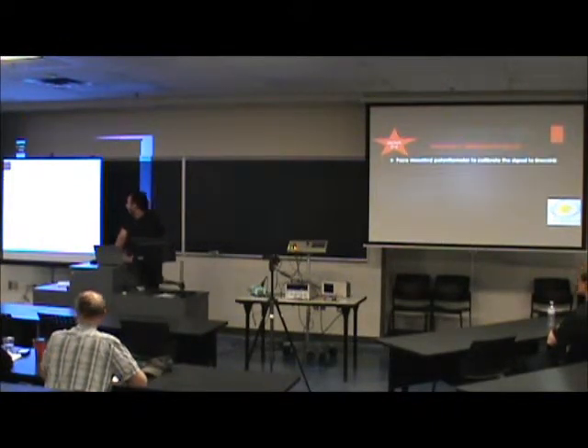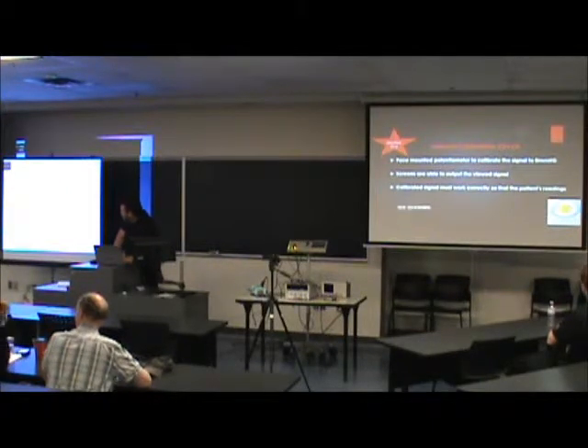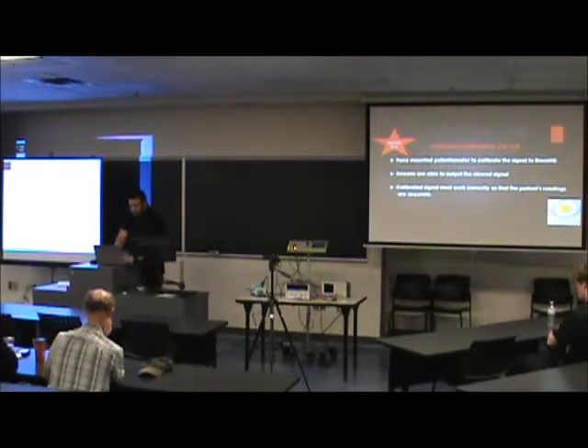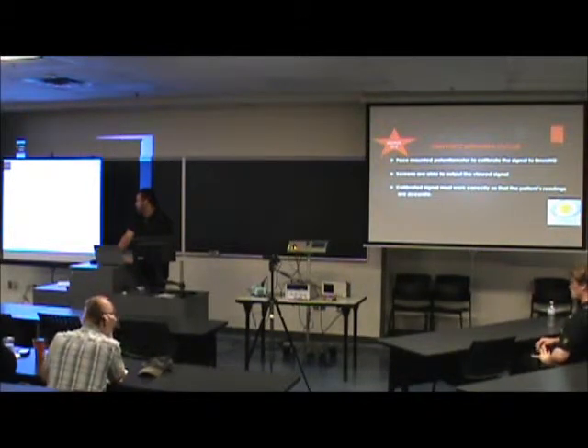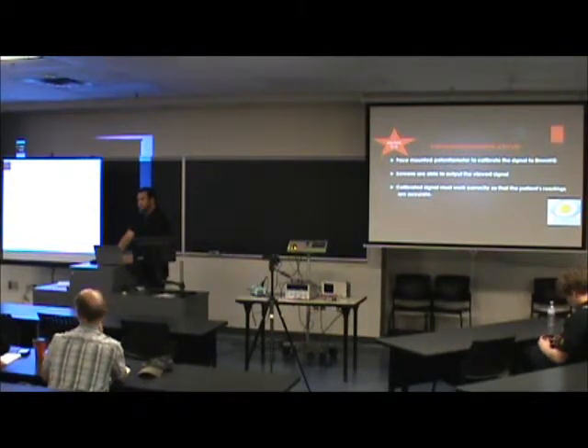So the internal calibration circuit. We have a panel-mounted potentiometer for easy use to calibrate the signal to 0 millimeters of mercury. The screens are able to output the viewed signal, and the calibrated signal must work correctly so the patient's readings are accurate. The calibration must be done every 12 hours since the atmospheric pressure changes. We need to make sure that it is always 0 in order to have the correct reading afterwards.